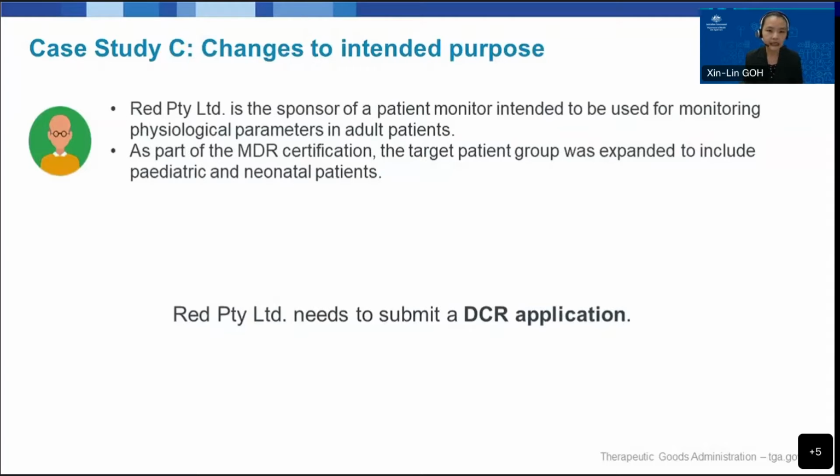And in case study C, we have Red, who is the sponsor of a patient monitor intended to be used for monitoring physiological parameters in adult patients. So as part of the EU MDR certification, the target patient group was expanded to include pediatric and neonatal patients. So in this case, Red will need to submit a device change request application to update their intended purpose in their ARTG entry.